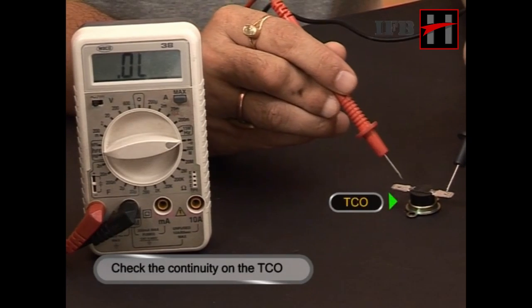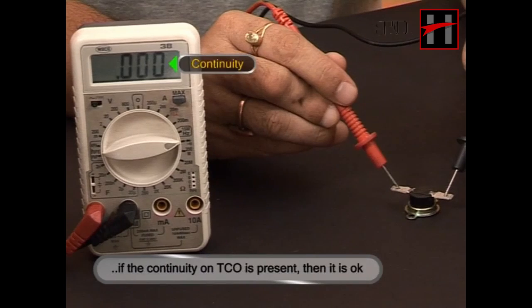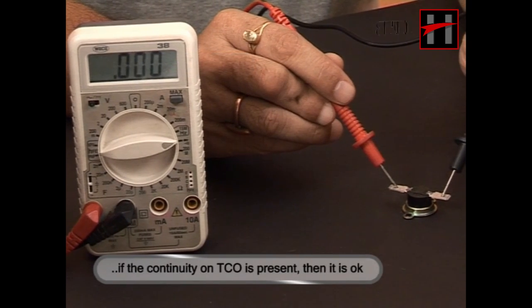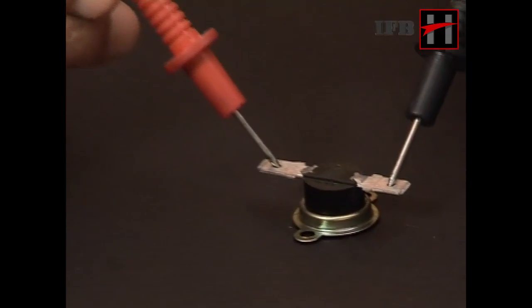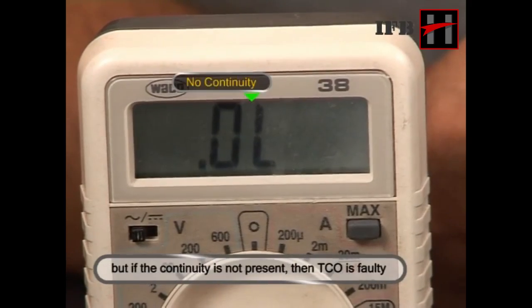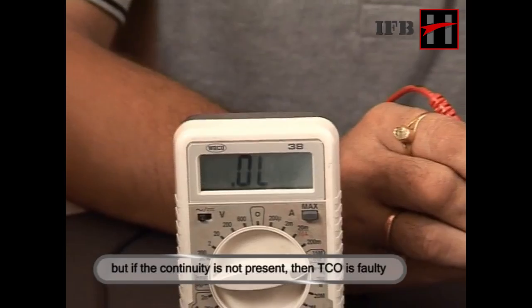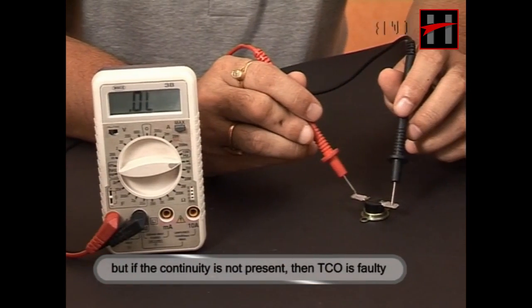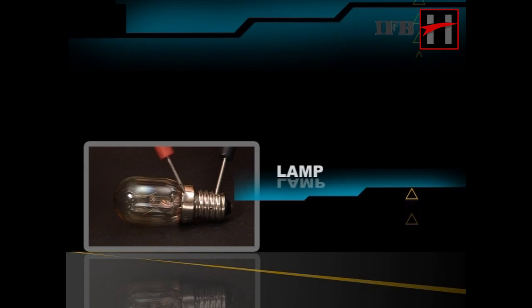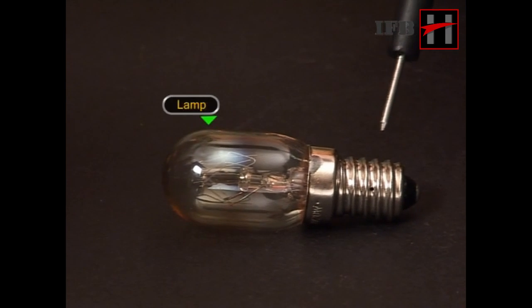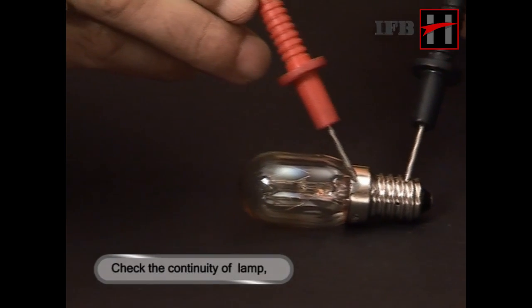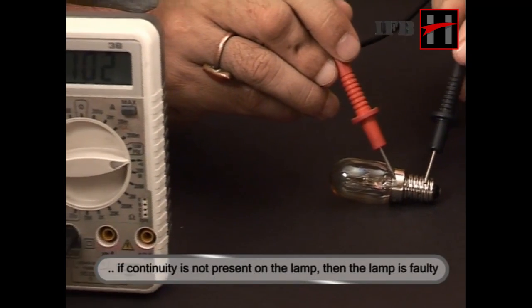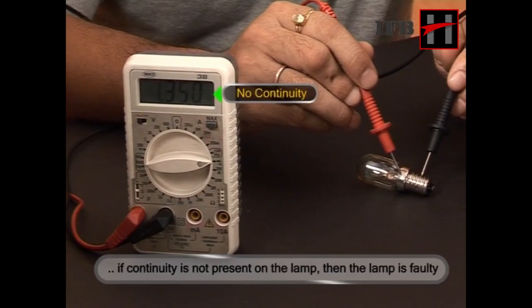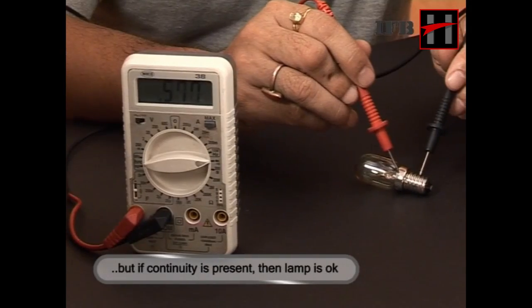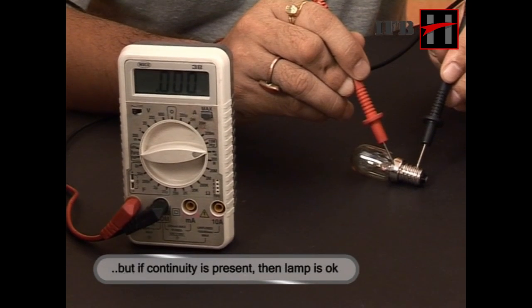Check the continuity on TCO. If continuity on TCO is present, then it is OK. But if continuity is not present, then the TCO is faulty. Check the continuity of lamp. If continuity is not present, the lamp is defective. But if continuity is present, then the lamp is in normal working condition.